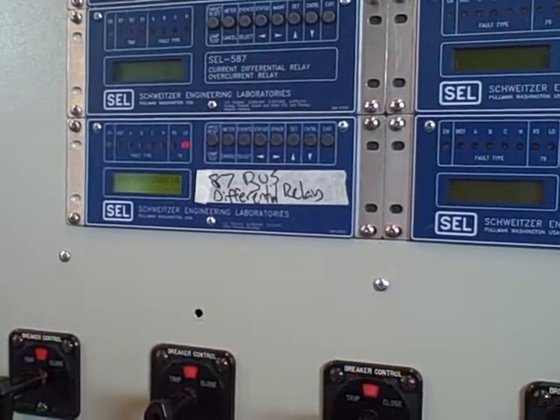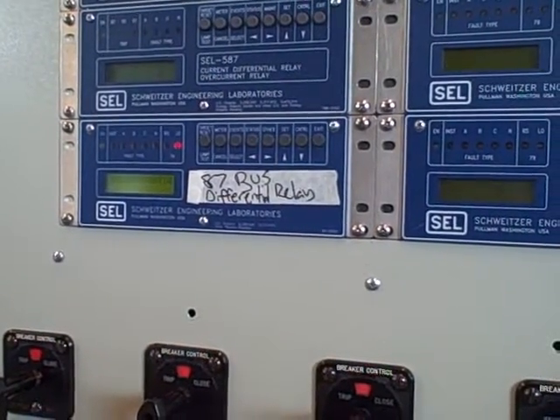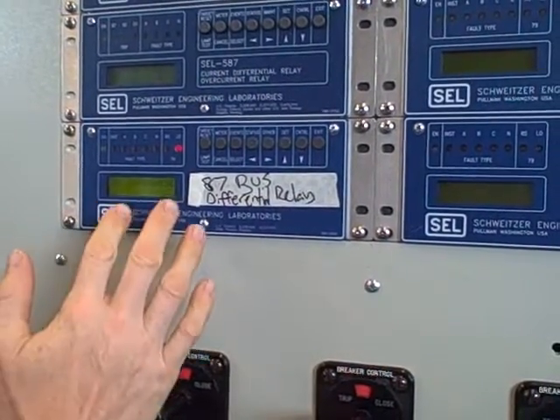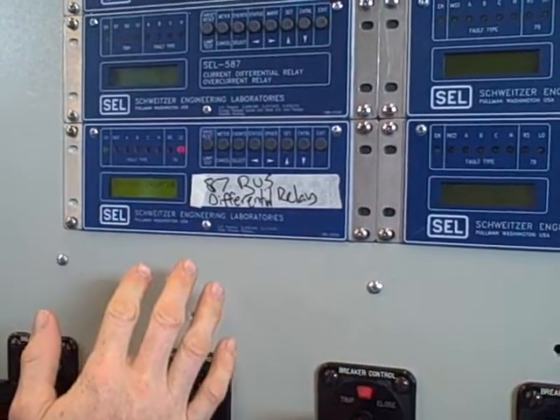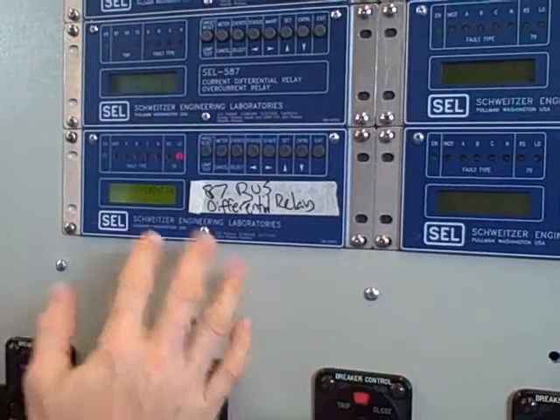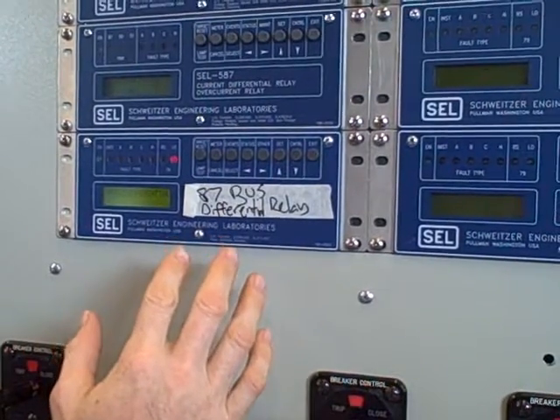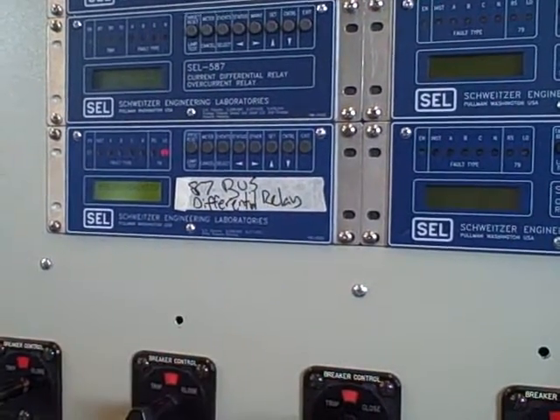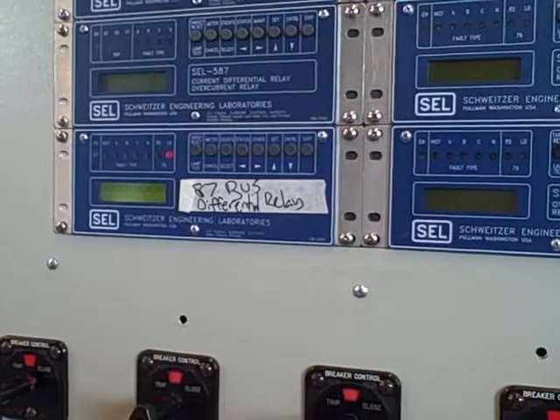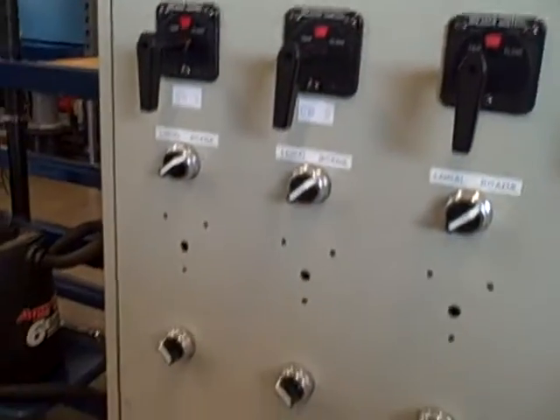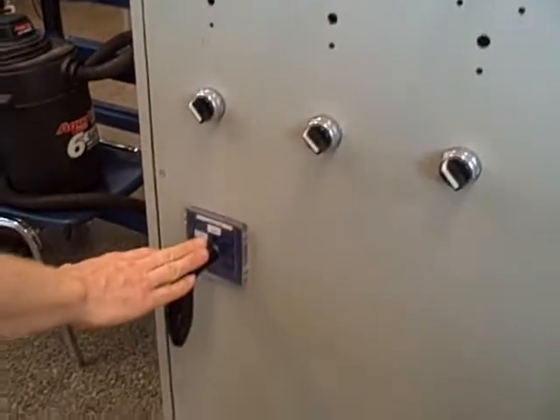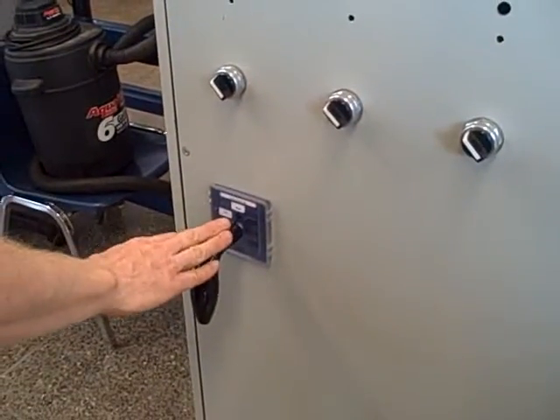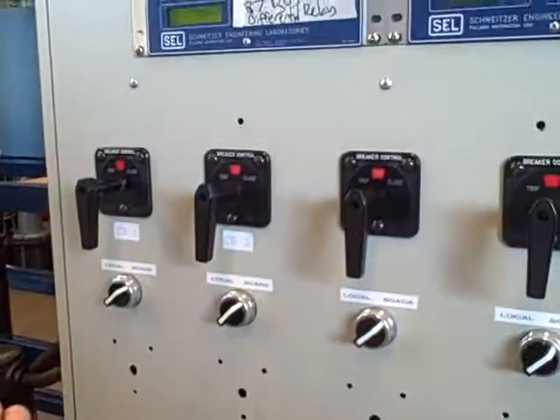What I'd like to demonstrate here is one of the features that you have with a digital relay: you can force the trip output contact to actually close. I'm going to do that to show how the lockout relay function on the substation works and how when that trips, it trips off all five circuit breakers.